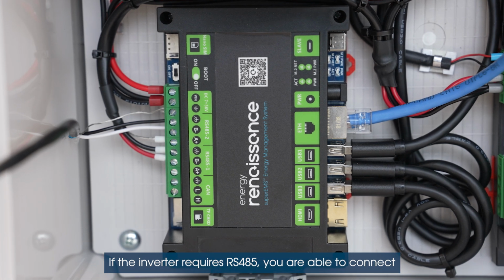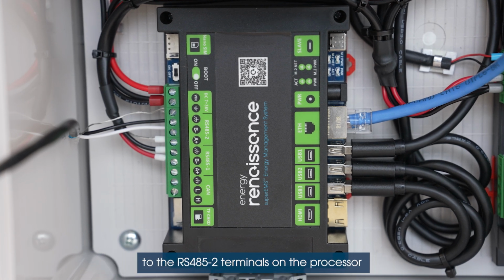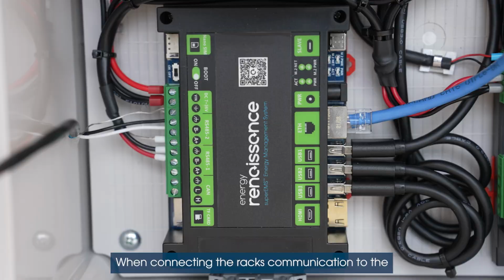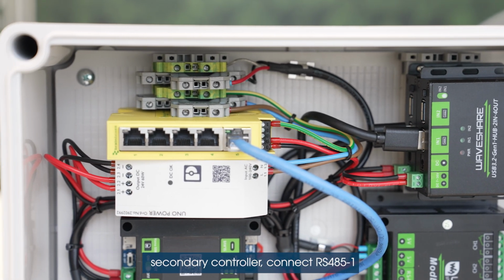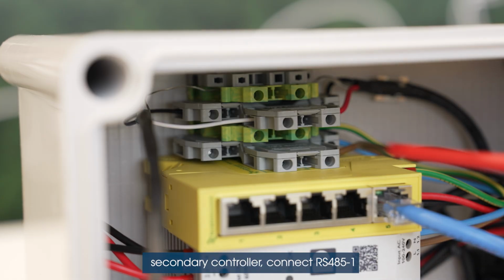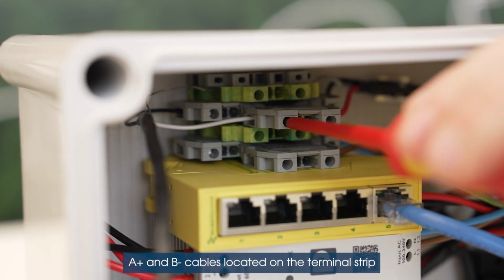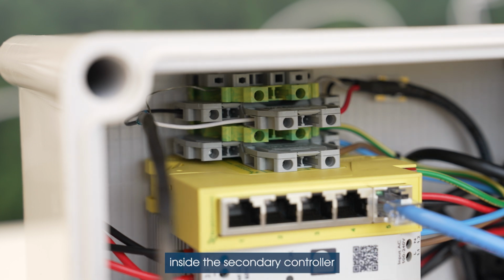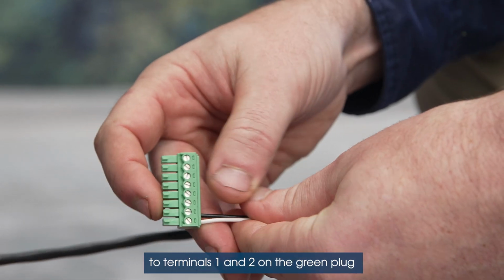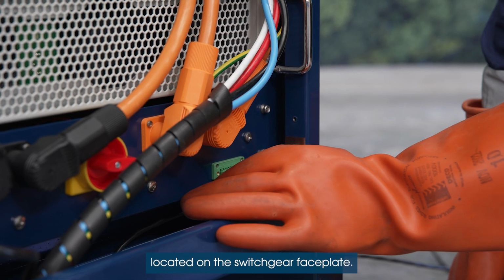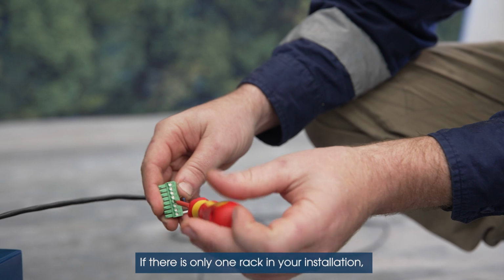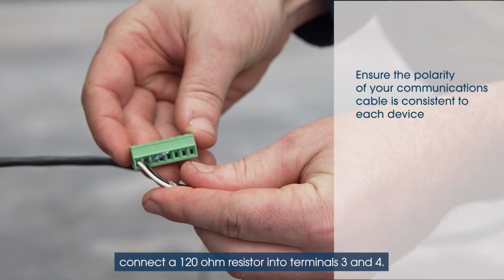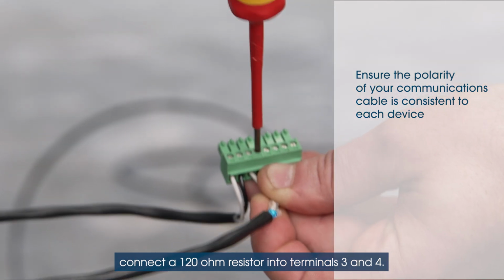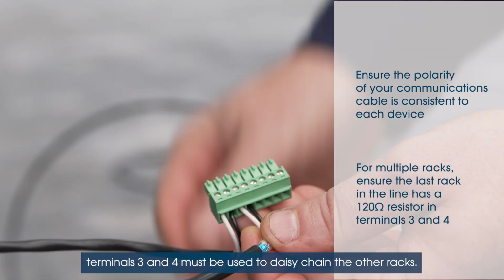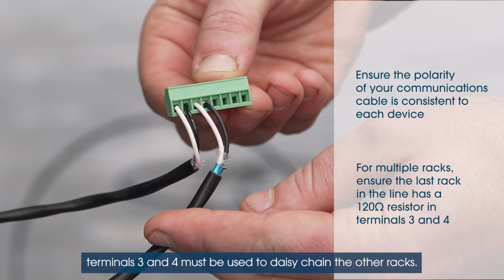If the inverter requires RS485, you are able to connect to the RS485-2 terminals on the processor inside the secondary controller. When connecting the rack's communication to the secondary controller, connect RS485-1 A positive and B negative cables located on the terminal strip inside the secondary controller to terminals 1 and 2 on the green plug located on the switchgear faceplate. If there is only one rack in your installation, connect a 120 ohm resistor into terminals 3 and 4. If the installation has multiple racks, terminals 3 and 4 must be used to daisy chain the other racks.